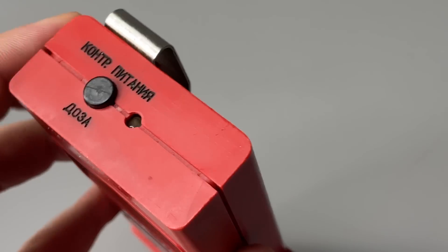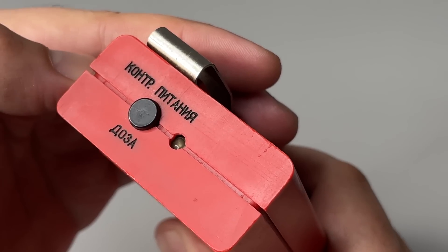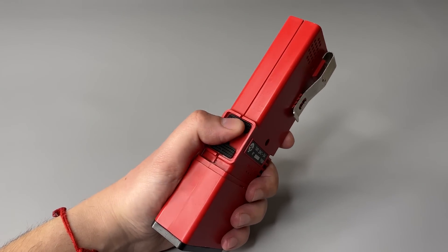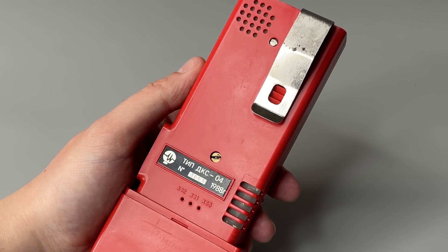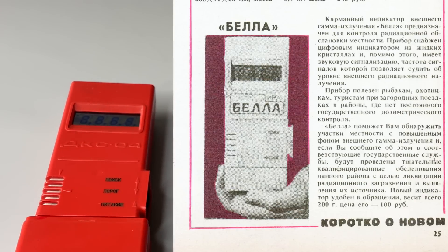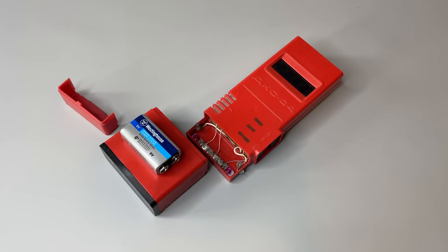On the top there's a button to see the dose received and check the power source, and next to it is the alarm LED which blinks from time to time. On the side is the power switch, and another toggle switches the mode between search and dose measurement. On the rear side there's an opening for the beeper and a connector optionally used for a frequency meter and oscilloscope during calibration with a standard check source. Visually it looks very similar to the popular Bella dosimeter intended for home use — the DKG-04 is always red, not white, gray, or brown like the Bella. Contrary to the Bella, the DKG-04 is powered by rechargeable D01 cells — seven of them — so a charger was included in the set, along with a battery pack allowing use of a standard 9V battery.